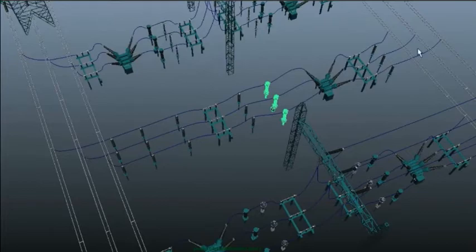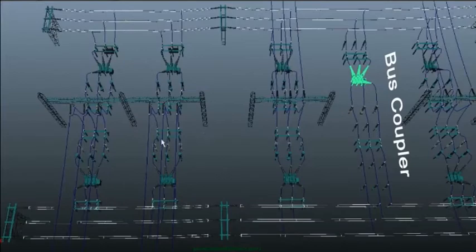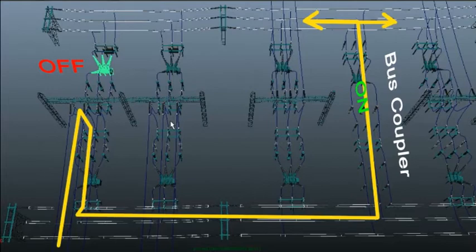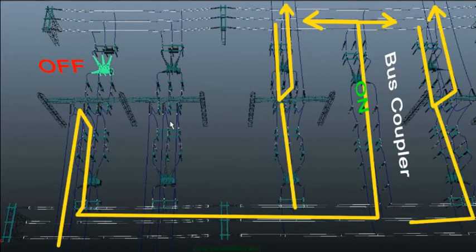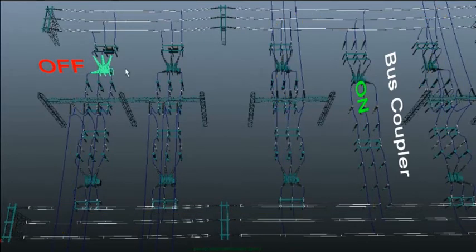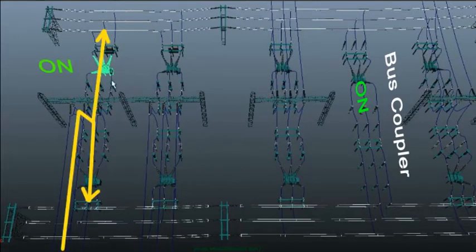Bus coupler is very useful during the time of maintenance. Like, to do the maintenance of this circuit breaker, the bus coupler must be switched on, so that the incoming power from this line will transfer to bus 2 through this path and finally reach the transmission line. So we will not face any problem in switching off this breaker. After getting done with maintenance of the circuit breaker, it could be put again in duty so that the power again reaches both the buses from this path. And the bus coupler could be switched off.